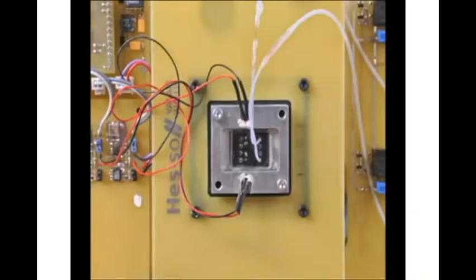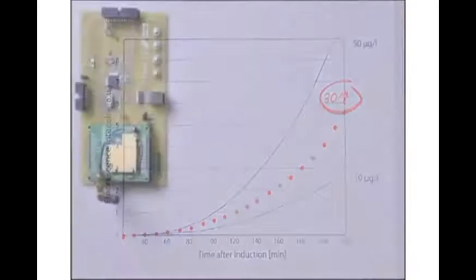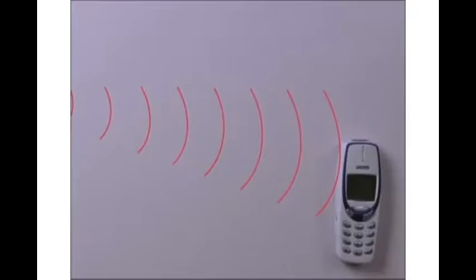The amount of GFP is a function of time and arsenic concentration. This is done by exciting the GFP with blue light and measuring the green fluorescent light after blocking the blue excitation light with an optical filter. Repeating these measurements every five minutes allows calculation of the arsenic concentration. The results are sent via a GSM module to a mobile phone.